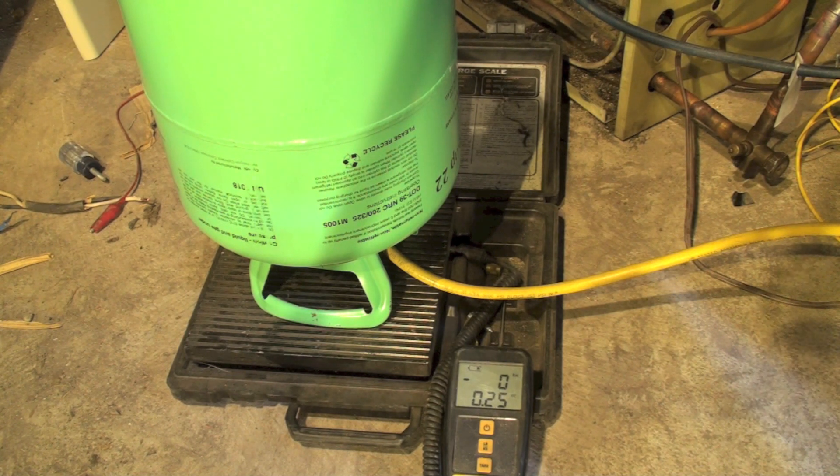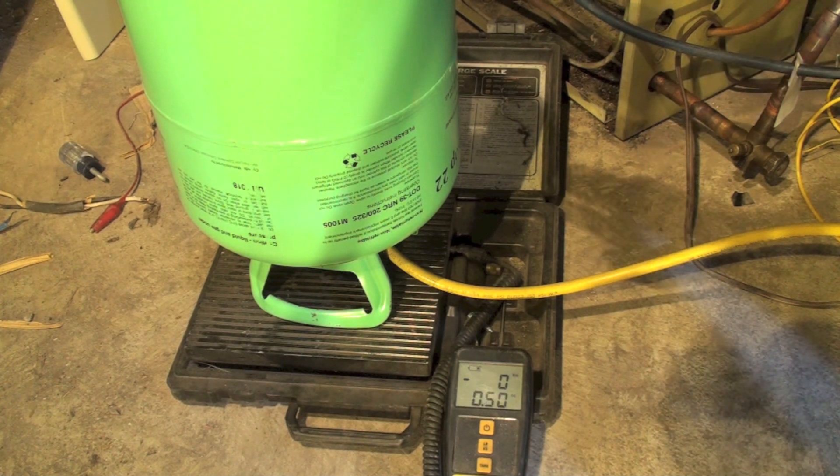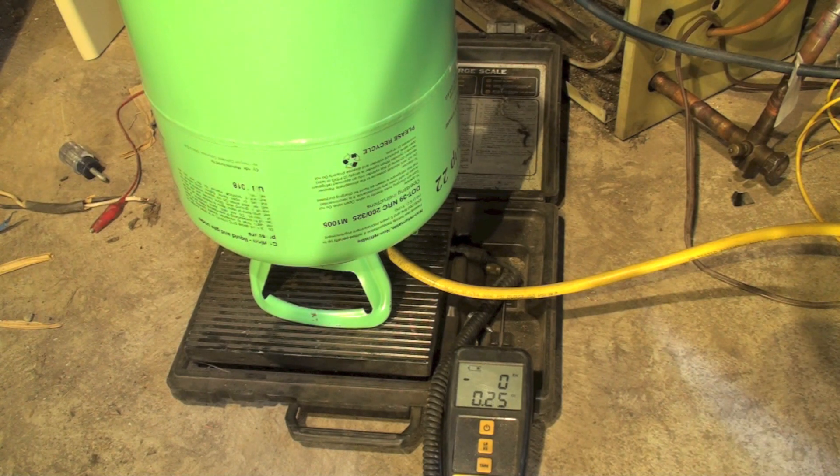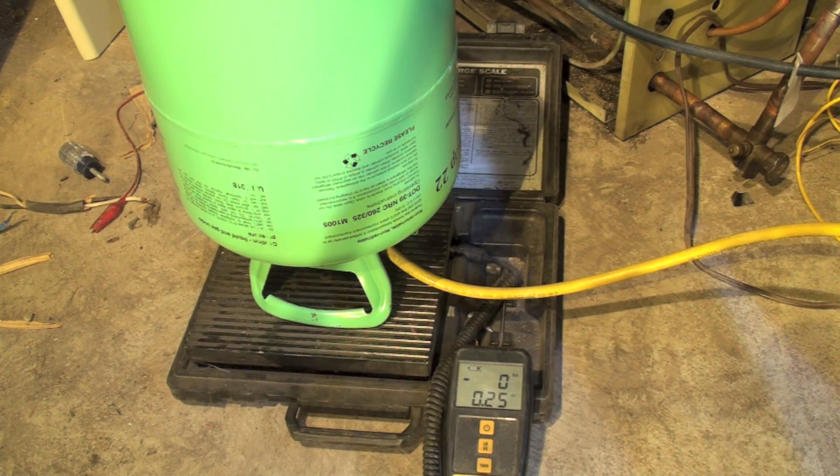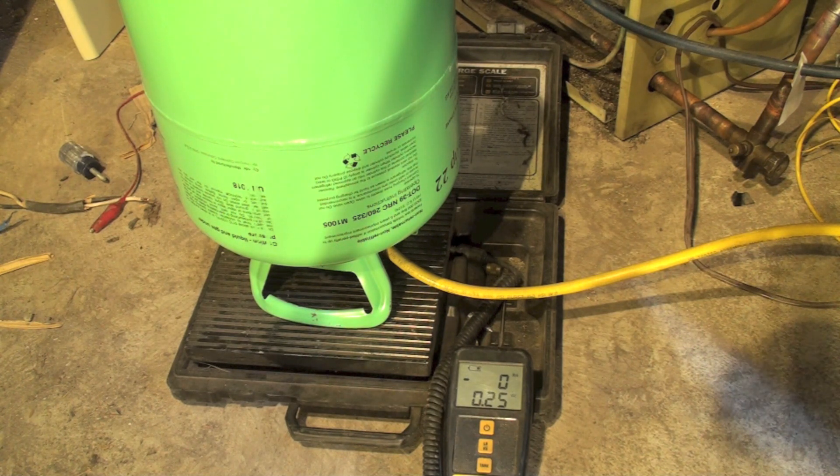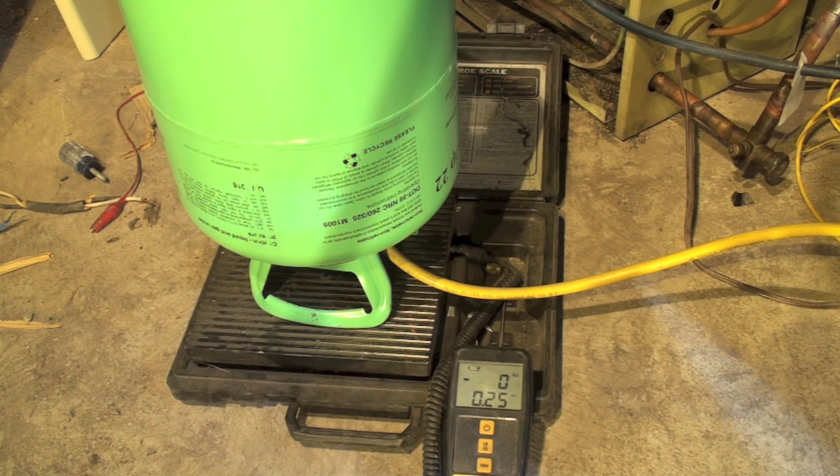We're just going to dump it in. The pressure inside this cylinder is going to push it into the high side. We only have like 13 pounds of pressure in there now. We're going to let the high pressure in the cylinder push it into the high side, get as much as we can in here without going over the total amount.